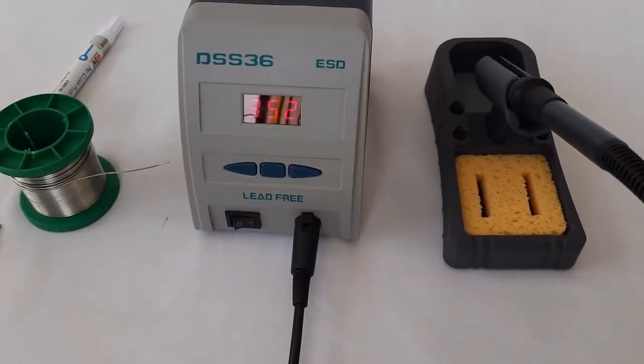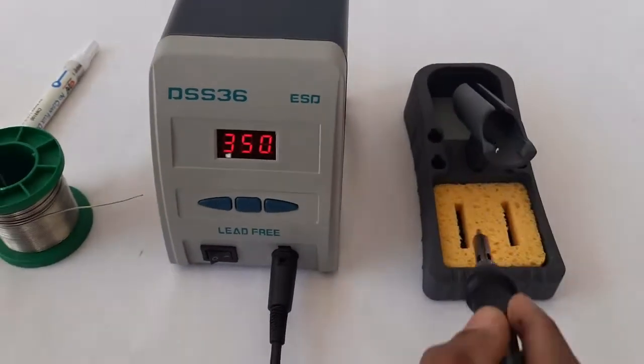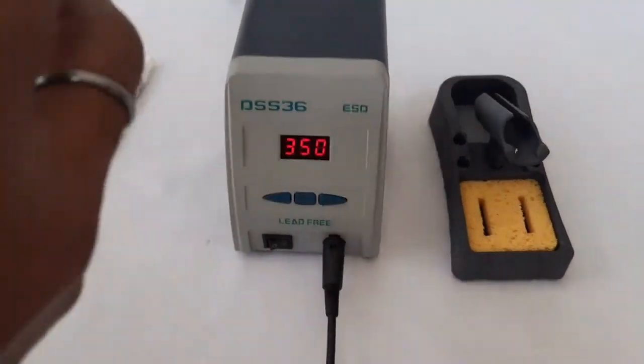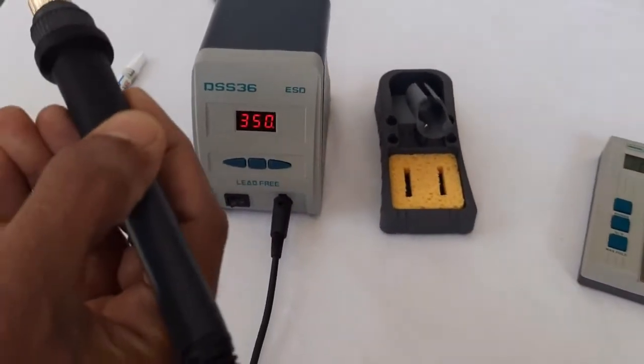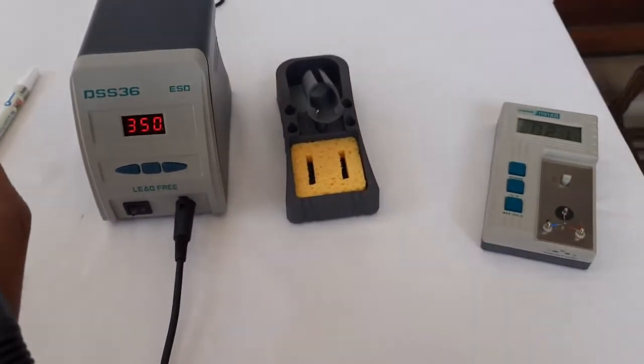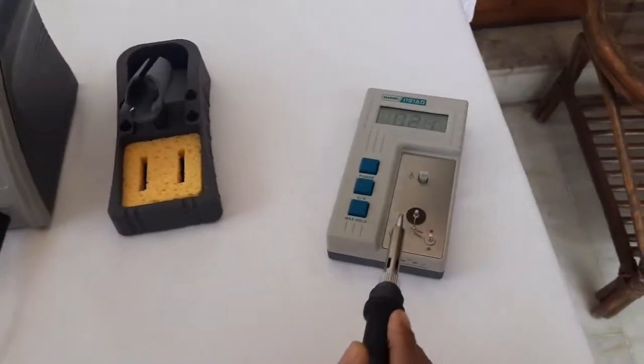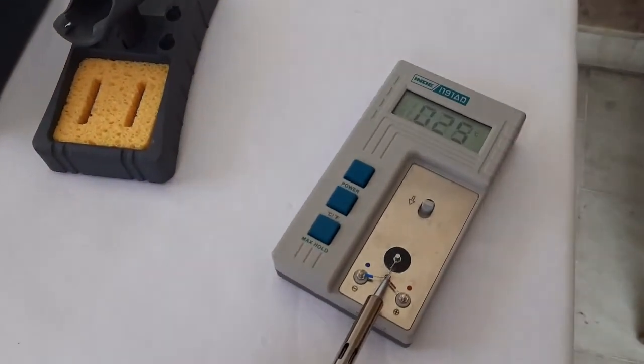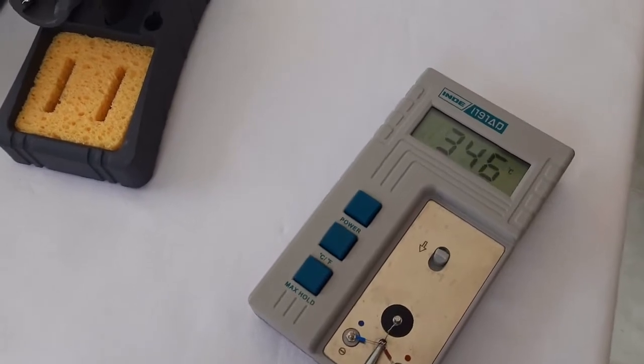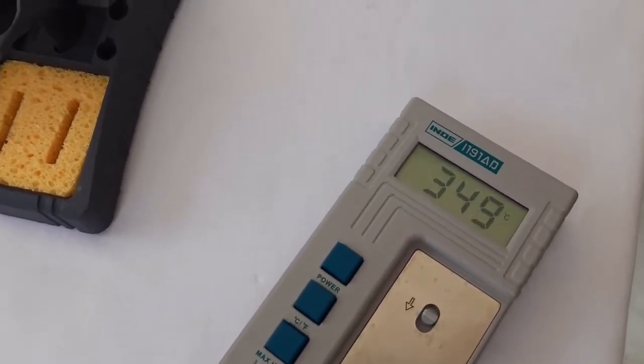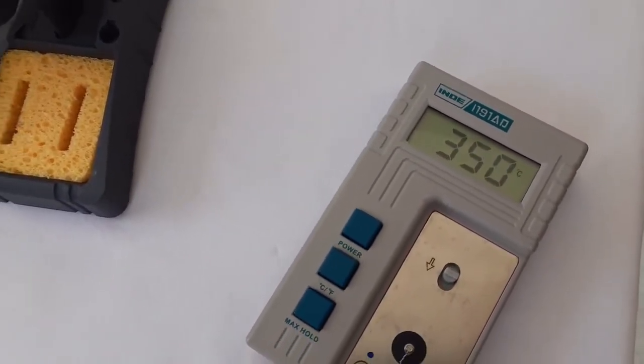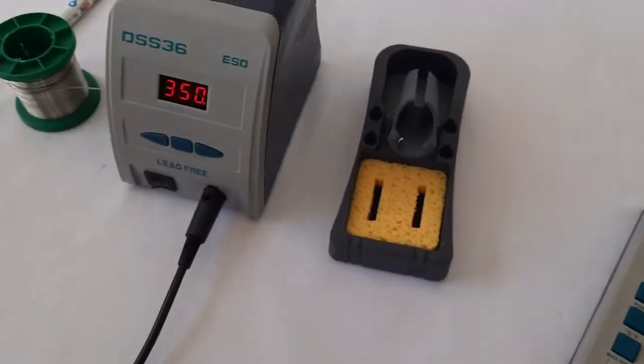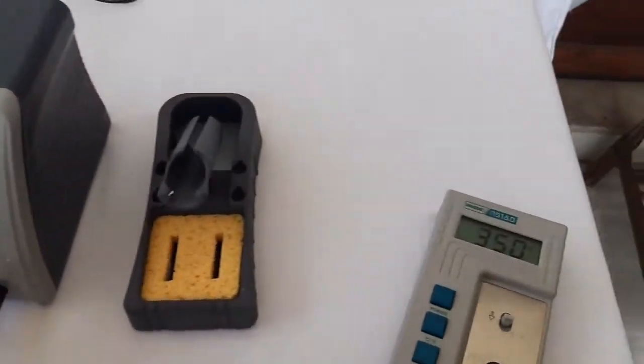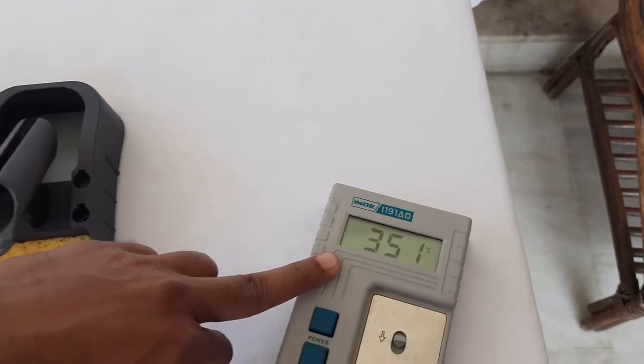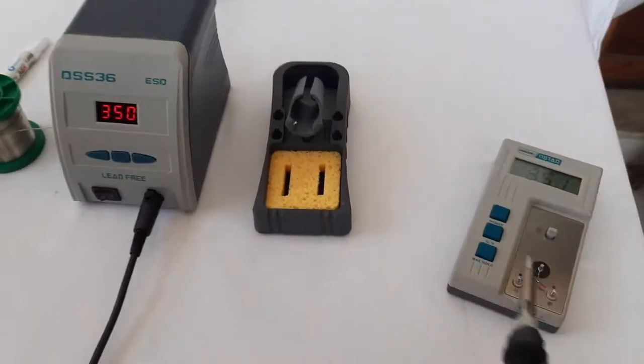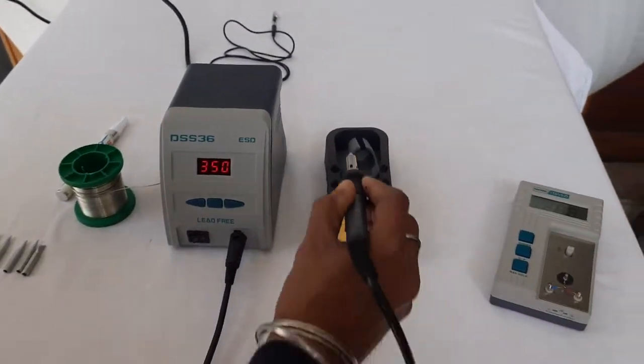Now we will again measure the tip temperature to see if the offset value we have given is accepted. Yes. Now the actual temperature and the set temperature are almost matching, 350 degrees on the display and 350 degrees on the calibrator. So this is how the calibration is done.